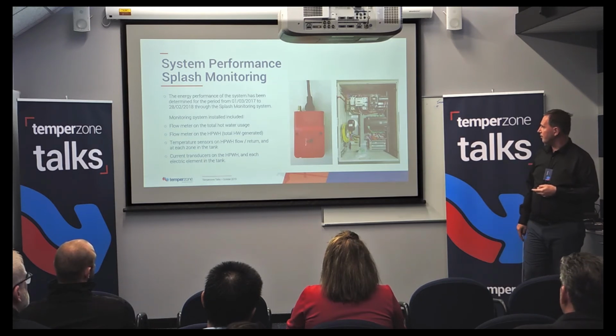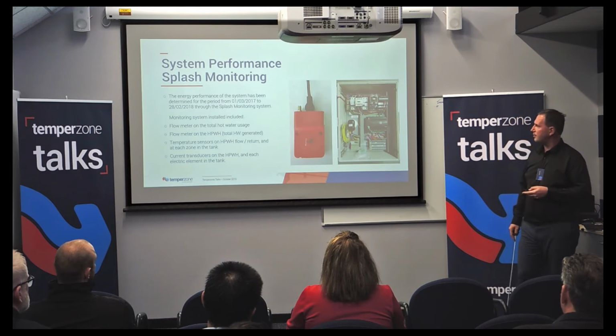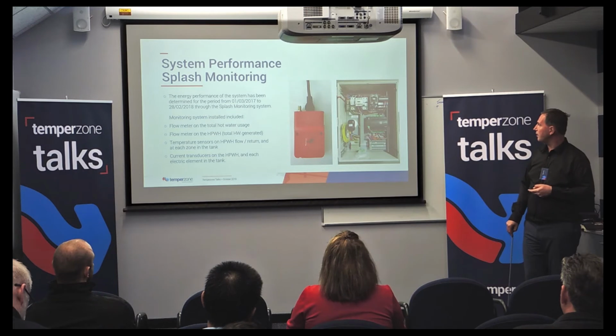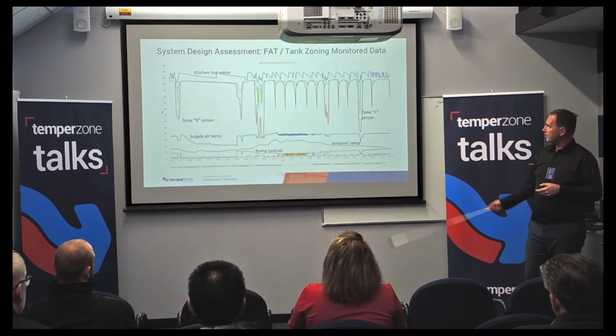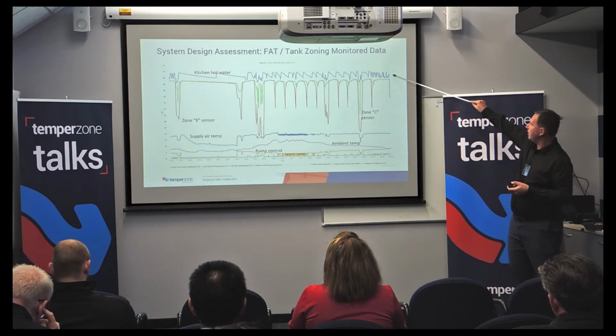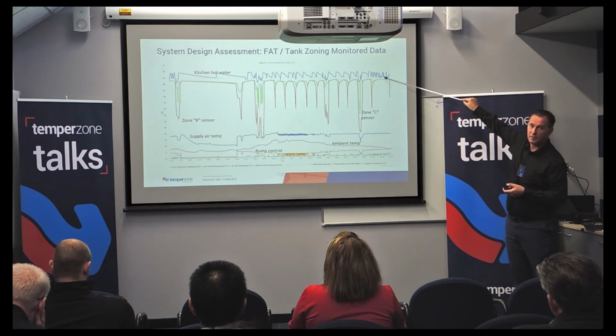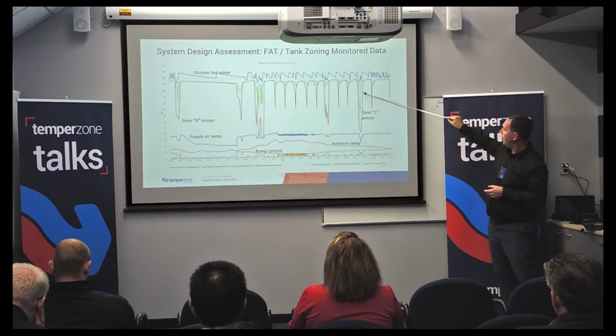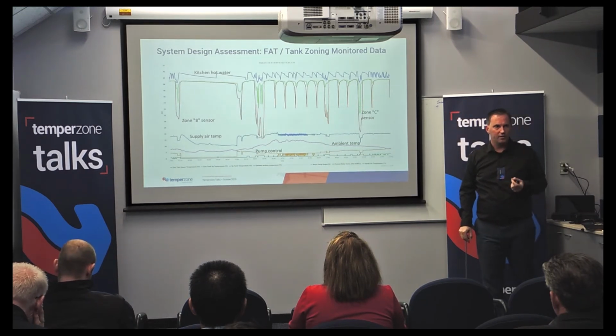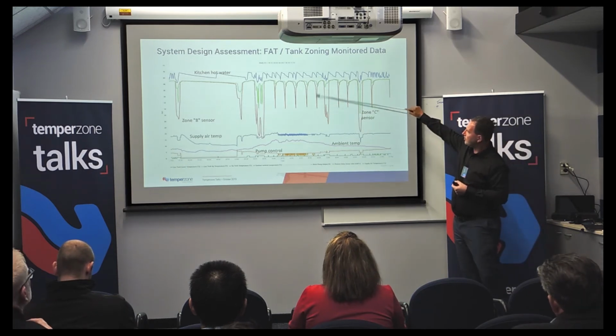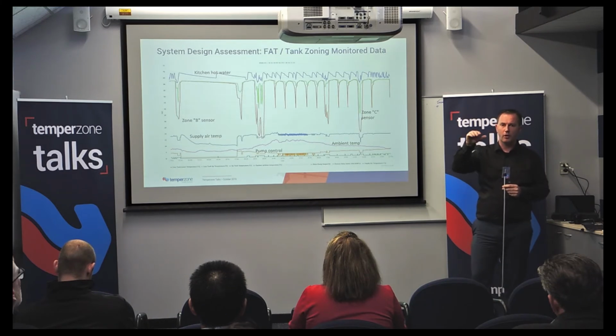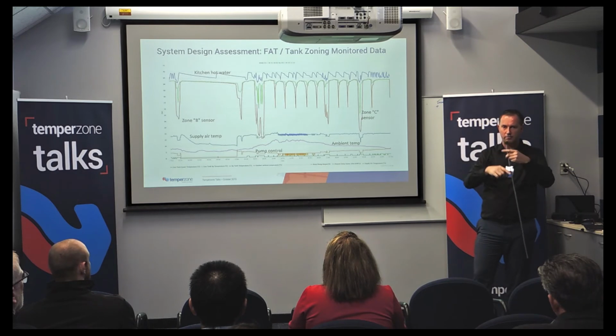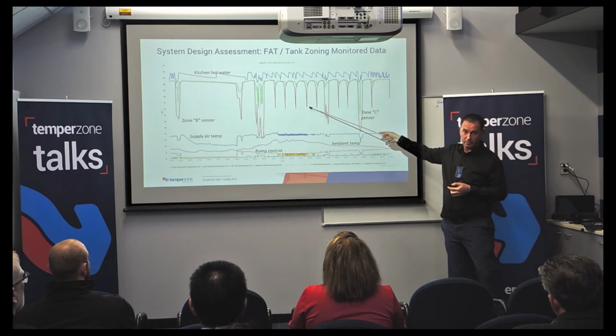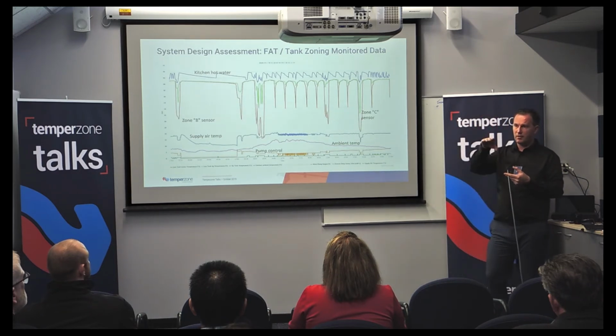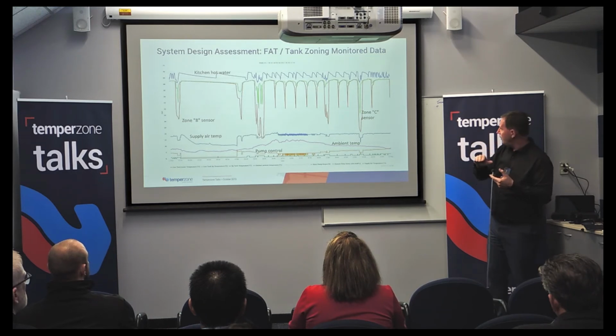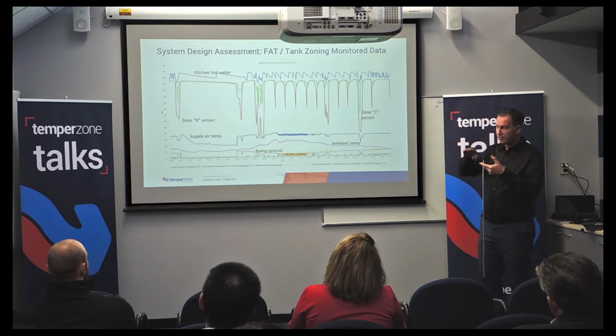And we've got a monitoring system where we had flow meters and temperature sensors around the system to calculate the energy consumption. And this is a day of use. So you can see the domestic hot water balancing around is fully timed back. This is the top element, the top of the tank. You can see how well thermally stratified this tank is. Each of these spikes here are this boundary layer between cold and hot, passing past a sensor in the tank. And you can see how sharp they are as the temperature changes, with such definition as it passes past this point.